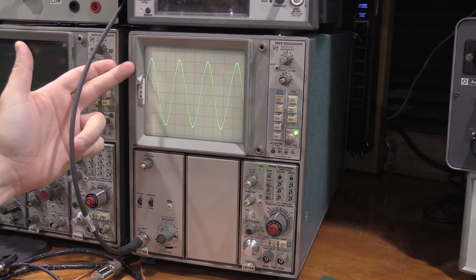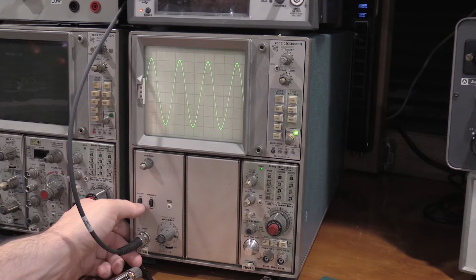So we do have a decent amount of signal coming from my function generator, and we have a nice clean sine wave, no noise. If I move this a little bit, there's a little noise in the switch, but that's typical with cam switches. Do have control on the variable. If I go to DC, we do have control. Full bandwidth, 20 megahertz. Bandwidth limit's fine. I can invert the polarity. So that looks like it's working.